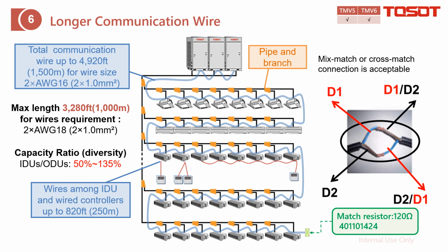And for the CAN, there is no polarity, which means on the wiring, you don't need to memorize the colors. Just connect it like this; mismatch or cross match is okay. And the total length for the D1, D2 can be up to 1.5 kilometers. And of course, the wire size should be this one. And the capacity ratio, or the diversity, the default setting is 50% to 135%. As for the indoor unit to the wired controller, the total length can be up to 250 meters.